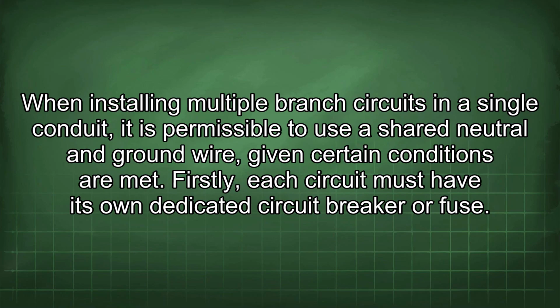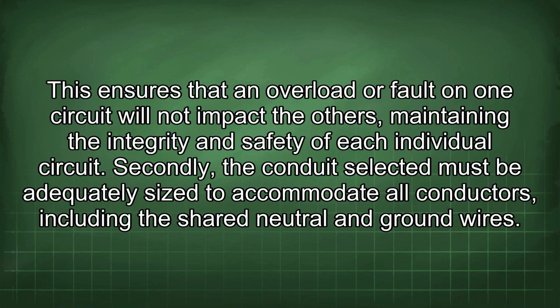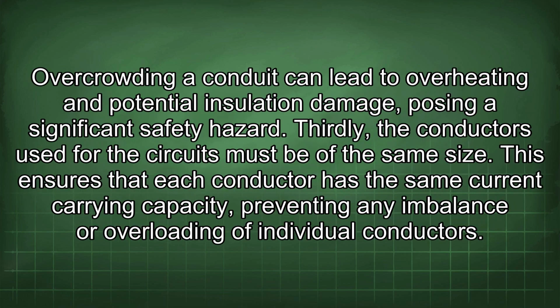When installing multiple branch circuits in a single conduit, it is permissible to use a shared neutral and ground wire, given certain conditions are met. Firstly, each circuit must have its own dedicated circuit breaker or fuse. This ensures that an overload or fault on one circuit will not impact the others, maintaining the integrity and safety of each individual circuit. Secondly, the conduit selected must be adequately sized to accommodate all conductors, including the shared neutral and ground wires. Overcrowding a conduit can lead to overheating and potential insulation damage, posing a significant safety hazard.